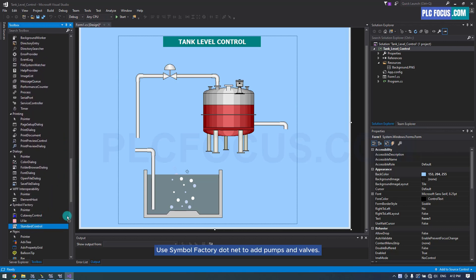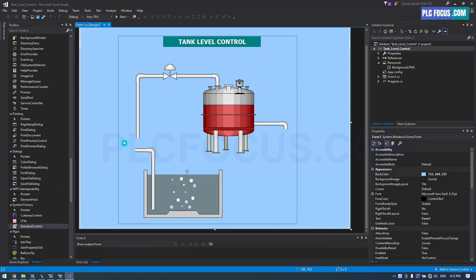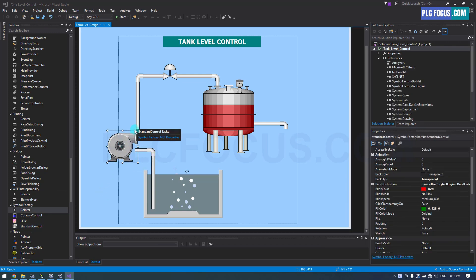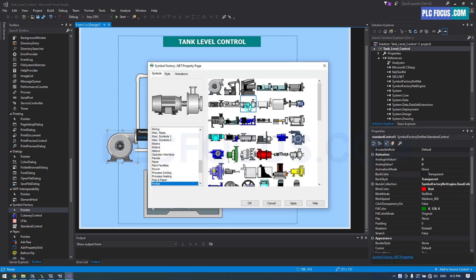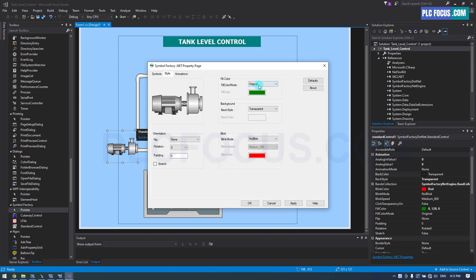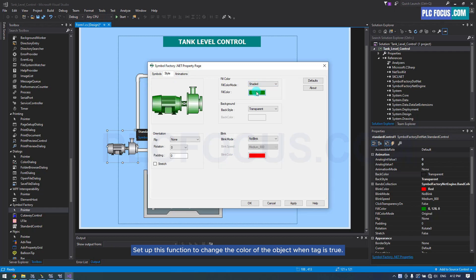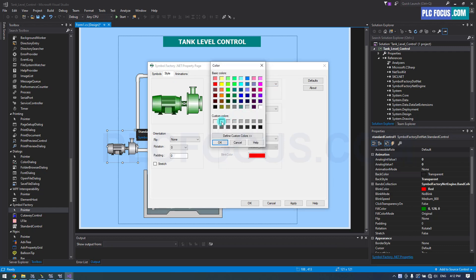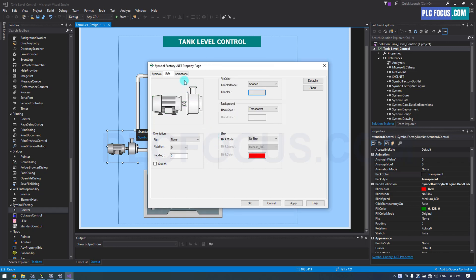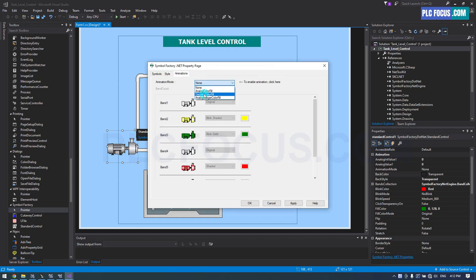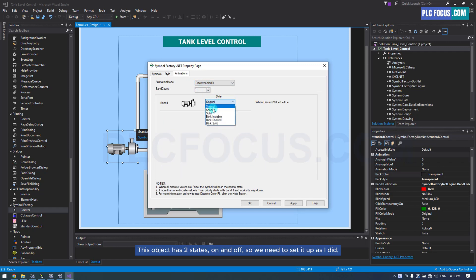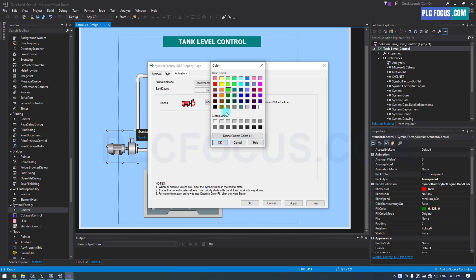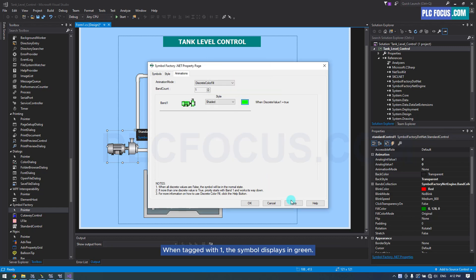Use Symbol Factory.NET to add pumps and valves. Change the icon to a pump. Set up this function to change the color of the object when the tag is true. This object has two states — on and off — so set it up accordingly. When the tag is 1, the symbol displays in green.